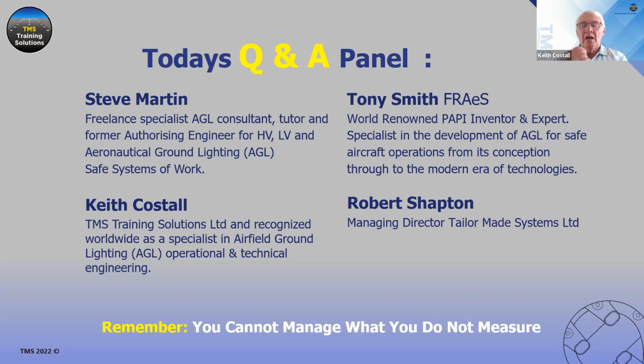So there's a range of good, competent connector suppliers in the marketplace globally. But remember, when things are new, you can achieve the ultimate. Where do they live? In the ground, in transformer pits, etc. Over time, products deteriorate, and it's that period of time and the deterioration rate that is the problem. It can come back to the installation technician if they have not followed the guidance for correctly installing and fitting those connectors.